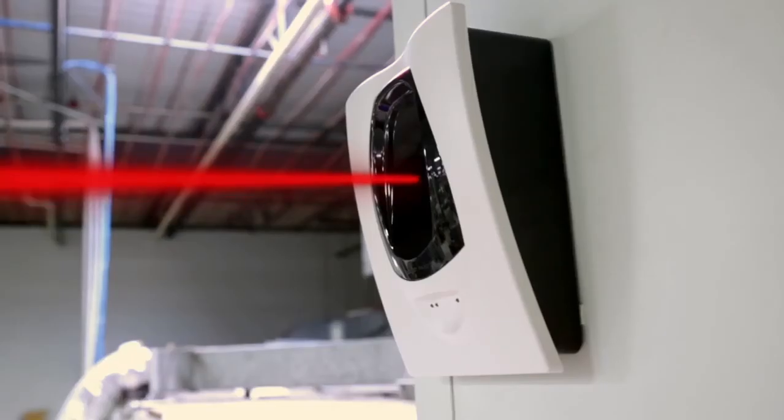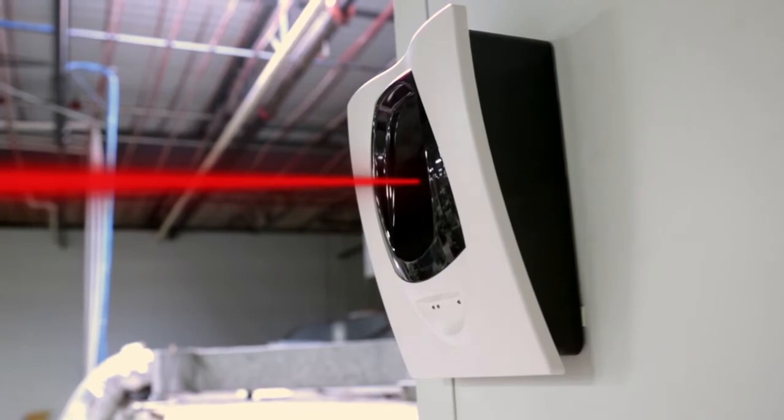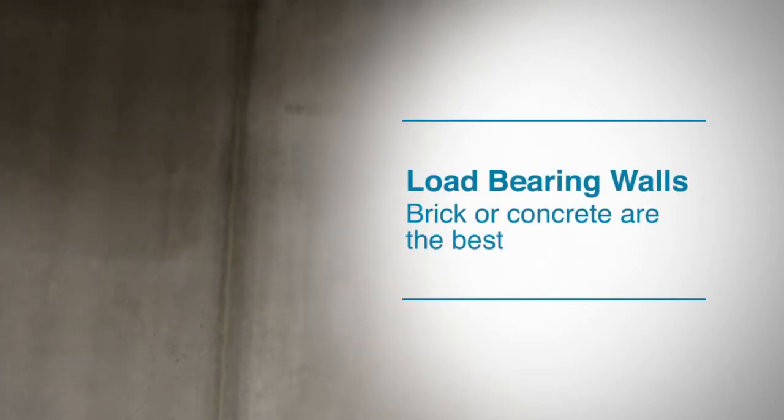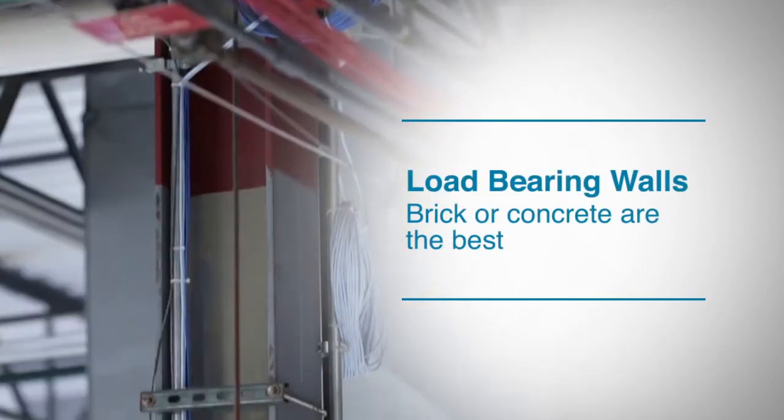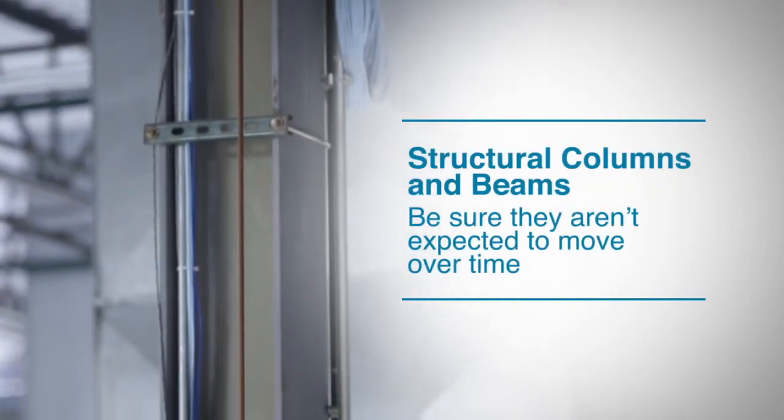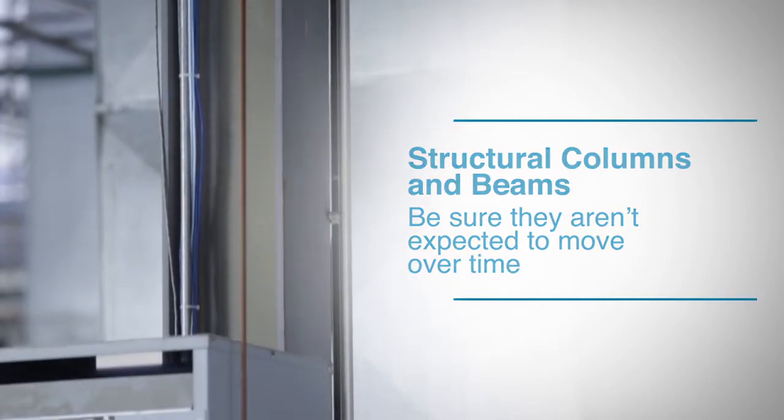Beam detectors require a stable mounting surface. Even small movements are amplified tremendously when shooting a beam hundreds of feet across an open space. Load bearing walls, particularly if they are brick or concrete, make the best mounting surfaces. Structural columns and beams can work well too, as long as they aren't expected to vibrate or move over time.